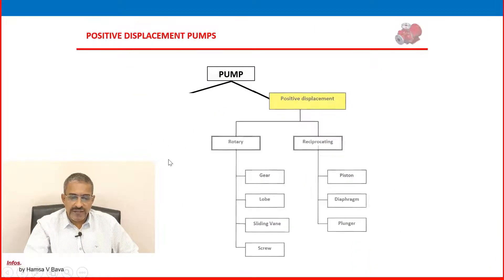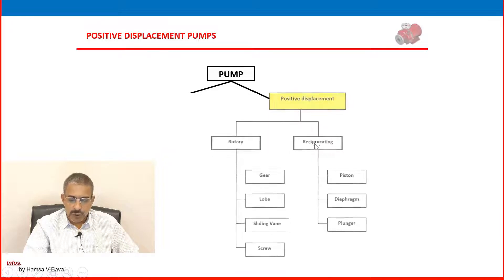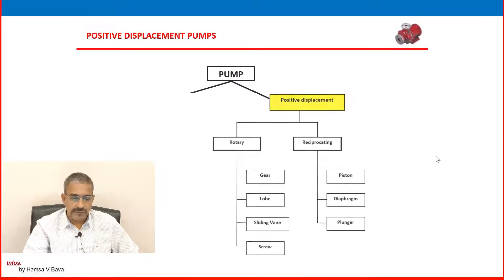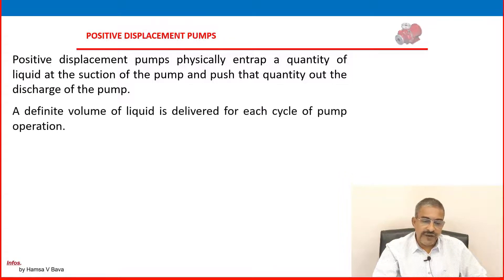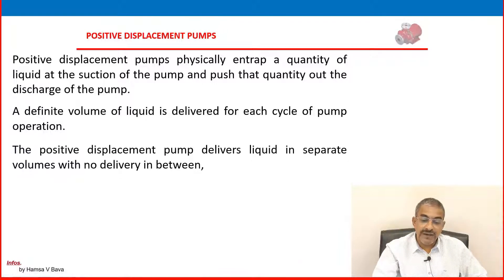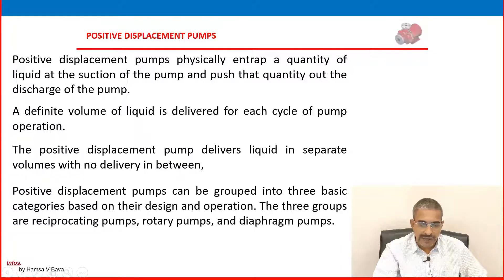In the positive displacement pump, there are two main classes: rotary and reciprocating. In this class, we are taking reciprocating pump — piston, diaphragm, and plunger. We will discuss rotary later. Positive displacement pumps physically entrap a quantity of liquid at the suction and push that quantity out at the discharge. A definitive volume of liquid is delivered for each cycle of pump operation. Positive displacement pumps can be grouped into three basic categories: reciprocating pump, rotary pump, and diaphragm pump.